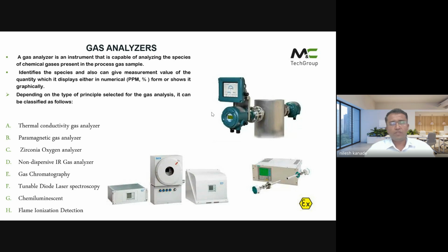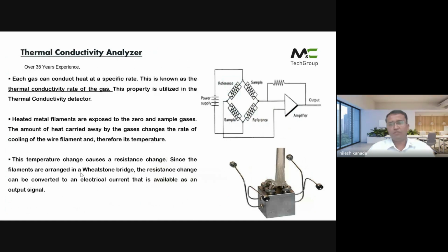There are a few measuring principles listed here: thermal conductivity gas analyzers, paramagnetic gas analyzers. The name itself is the measuring principle. Thermal conductivity is a property of the gas, and based upon that property, sensors are built in manufacturing facilities. These include paramagnetic gas analyzers, zirconia oxygen analyzers, non-dispersive infrared gas analyzers, gas chromatography (well known in the market), and the newer tunable diode laser spectroscopy, as well as chemiluminescence and flame ionization detection. These are the major process gas analyzer measuring sensors. Renowned manufacturers combine these sensors into their equipment to form gas analyzers. We'll first overlook the measuring principles, then go into their applications and discuss them.